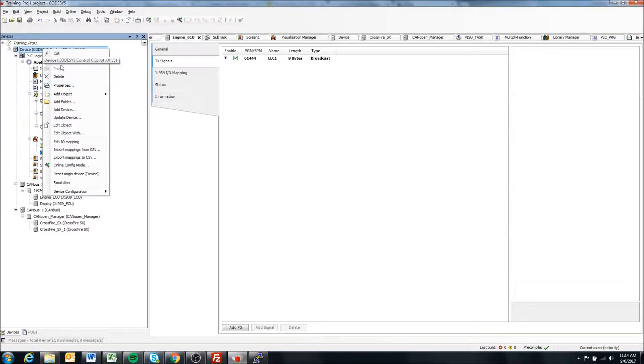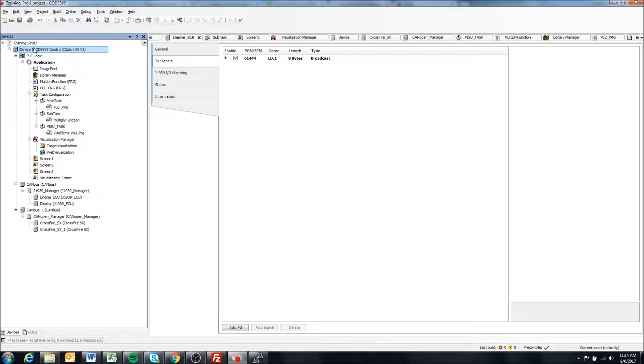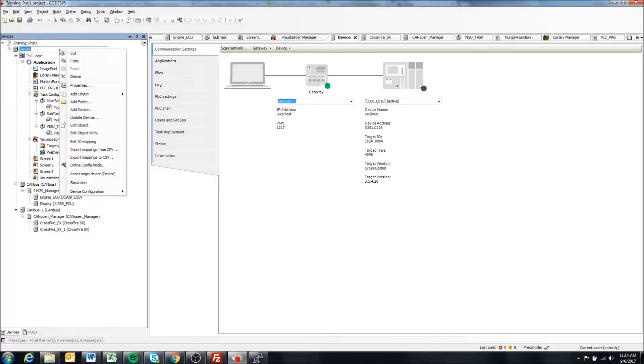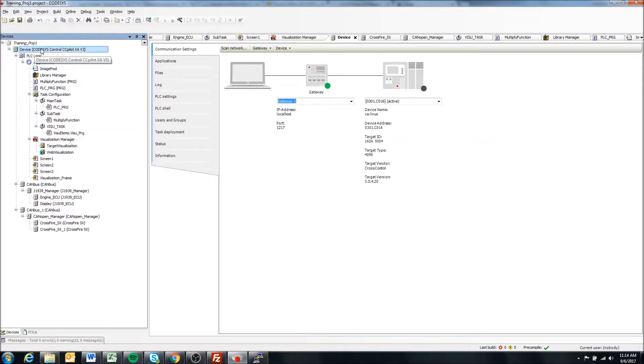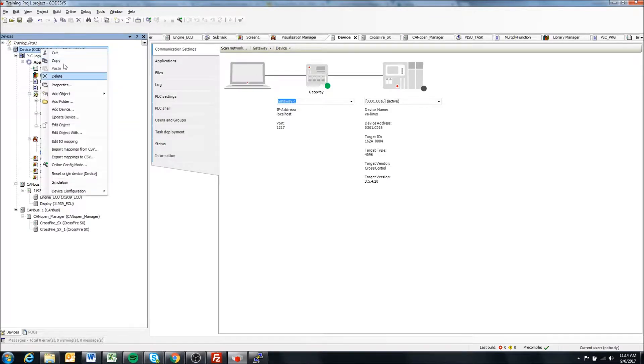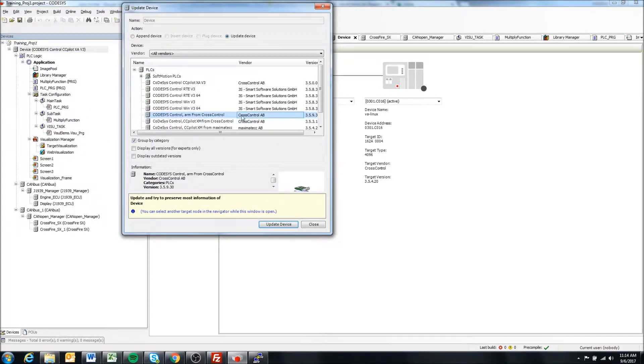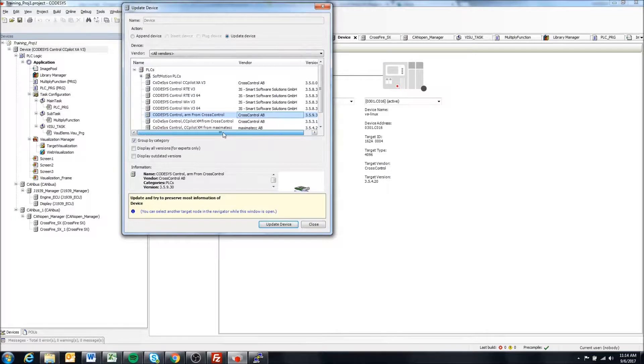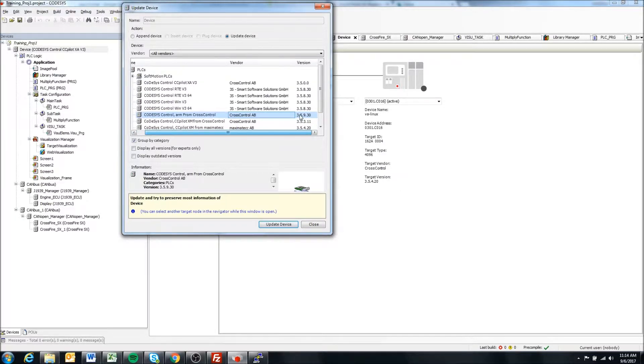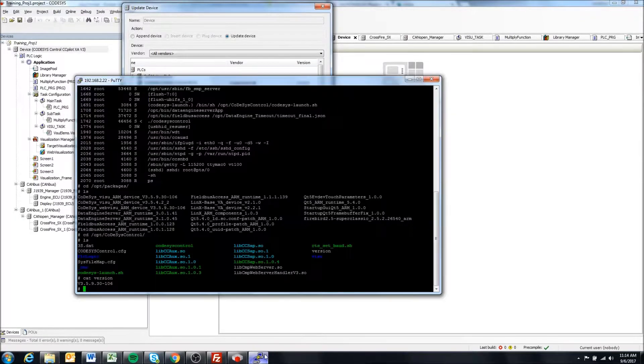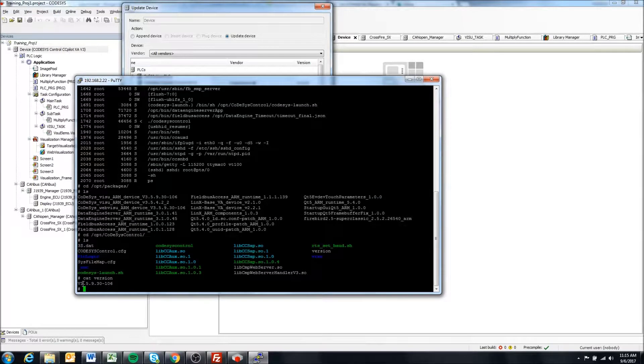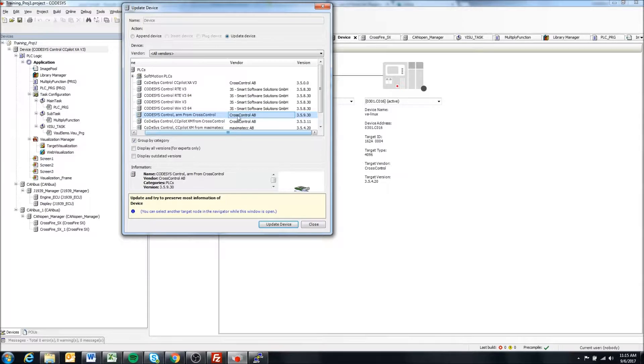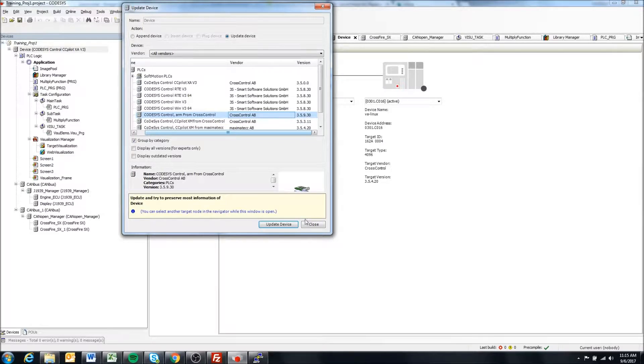Lastly, we can come into Codesys. We're just going to test out to see that we can connect. To make sure this is correct though, we want to make sure we have the correct device description here. We can say update device and look here. The device description version that we have, we want it to match the version of the runtime. We have 3.5.9.30 and the device description we're using is 3.5.9.30, so that's good.